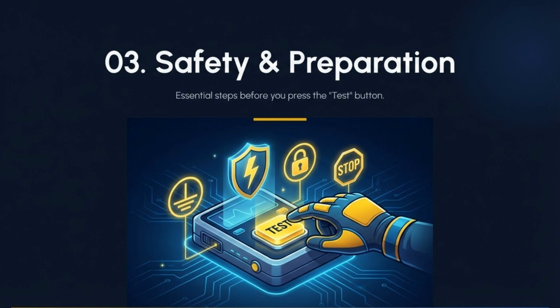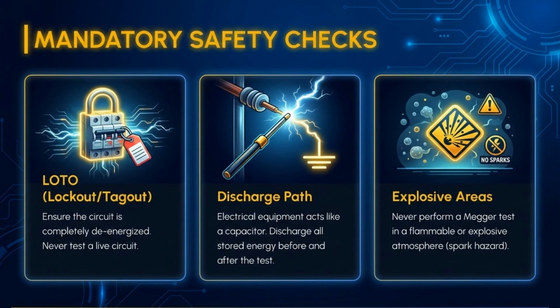Before conducting any test, safety and preparation are paramount. We'll cover the essential steps to take before pressing the test button. Mandatory safety checks include lockout/tagout, or LOTO, ensuring the circuit is fully de-energized. Use a discharge path to release all stored energy. Never perform a test in explosive areas due to the spark hazard.